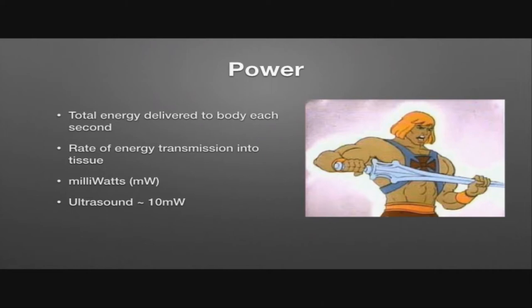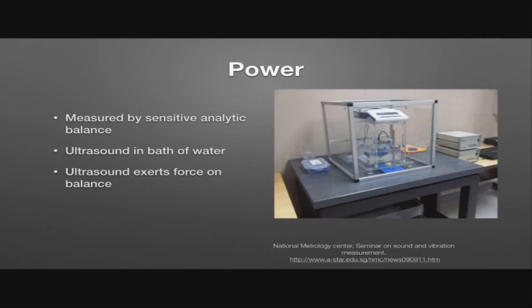Power is the total energy delivered to the body each second. We can look at this rate of energy transmission into the tissue and measure it in milliwatts. The typical value for diagnostic ultrasound is approximately 10 milliwatts. We can measure this using a very sensitive analytical balance — typically in a bath of water — essentially like kitchen scales but about a million times more sensitive. The ultrasound exerts a certain force on the balance, which gets picked up as long as the balance is sensitive enough.